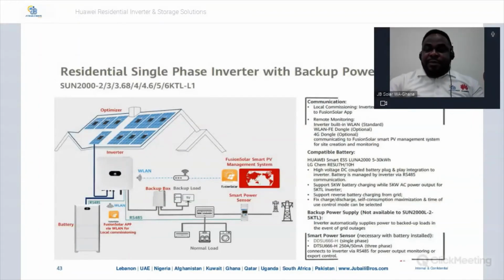I can put a DB, and then I'll connect all my critical load. In the event the grid goes off, I want my battery to power my lights, my television sockets, and a few other things. So I connect those loads to the critical DB. And then I leave my air conditioners, my washing machines, my dishwashers, I leave all of them on the main load. So when the light goes off, the battery will supply only the critical load and not every load in the house. This point is very important. That's why I took my time to explain it.